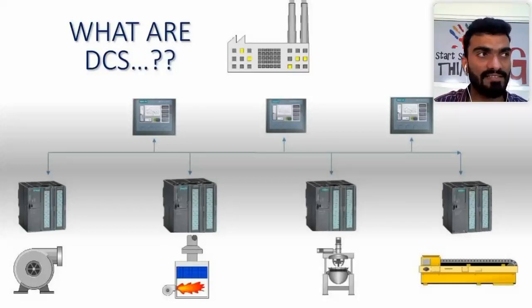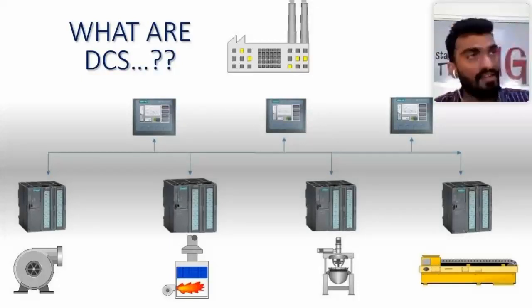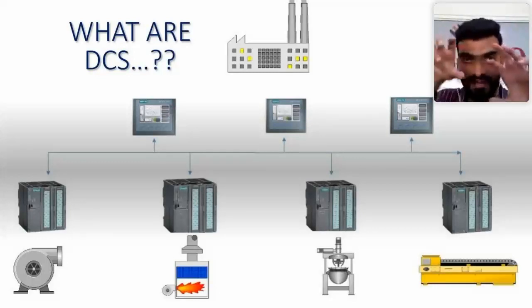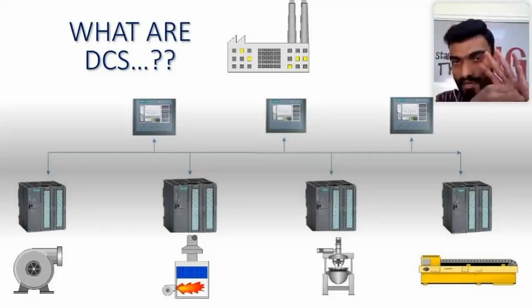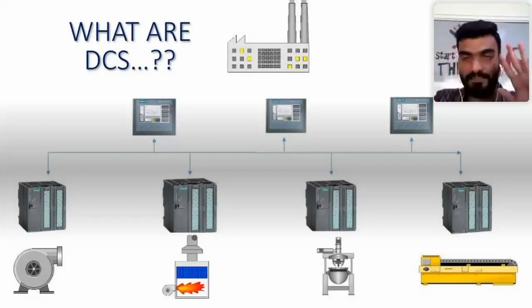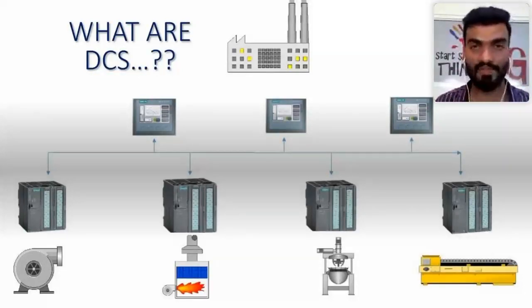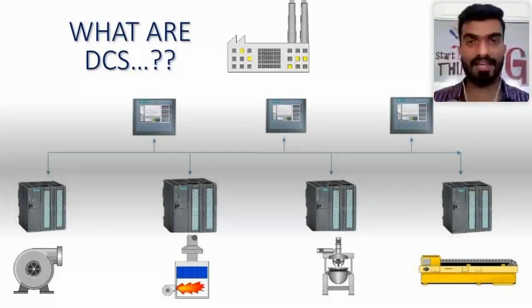The advantage is there are some ready-made function blocks available in the DCS. For each function you need not write a program. You can take the ready-made function blocks and connect the set of IOs to this function block, and it will monitor those particular IOs and give the statistics to the SCADA. This reduces the time, lets you control more PLCs and more IOs, and makes your controlling system easier. So this is all about DCS.